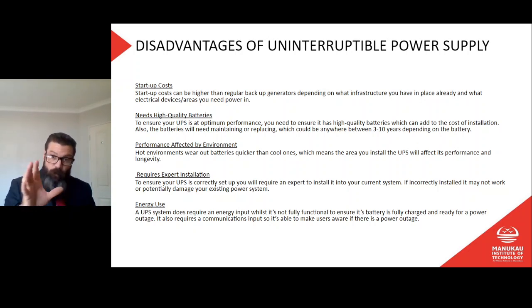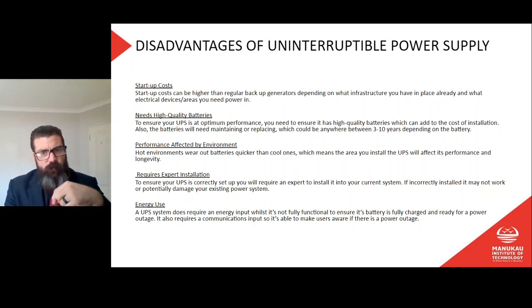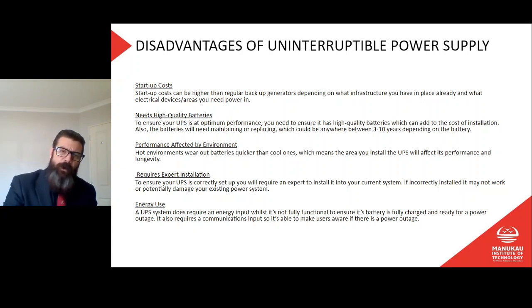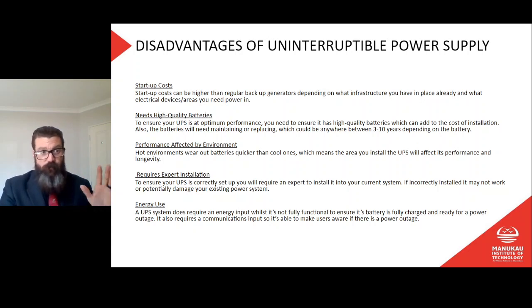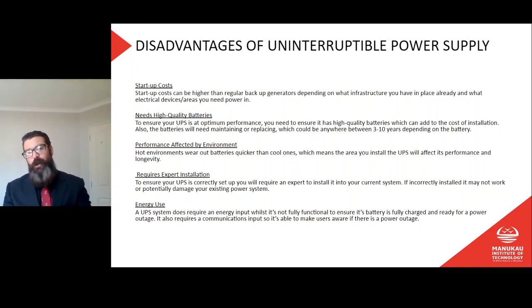So what I'll say about a UPS is, if you go into a building and it has a UPS connected to an outlet or a supply, what you need to be aware of is that when you unplug that UPS or kill power to the UPS, it will continue to provide output to whatever it's supposed to be providing output to. The UPS doesn't know, when you go into a building and isolate a circuit, that that's not a power cut. All the UPS knows is the power went off.